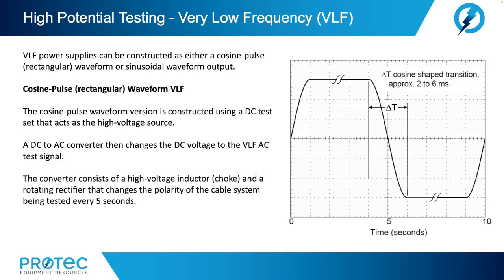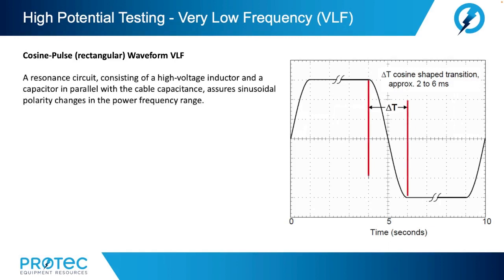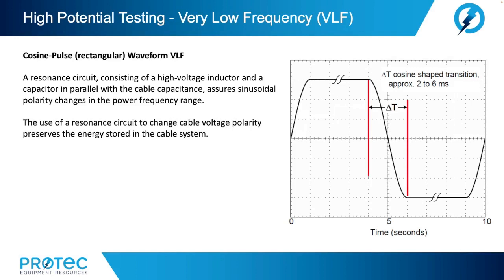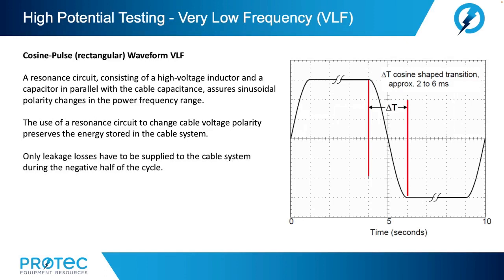The converter consists of a high voltage inductor or choke and a rotating rectifier that changes the polarity of the cable system being tested every 5 seconds. This generates the 0.1 hertz bipolar wave as we see here in the graphic. A resonance circuit consisting of a high voltage inductor and a capacitor in parallel with the cable capacitance assures sinusoidal polarity changes in the power frequency range. The use of a resonance circuit to change cable voltage polarity preserves the energy stored in the cable system. Only leakage losses have to be supplied to the cable system during the negative half of the cycle.